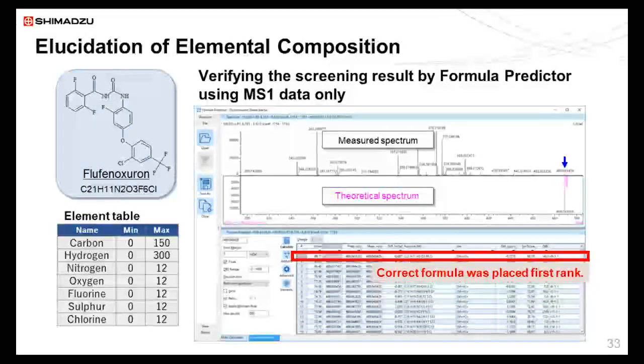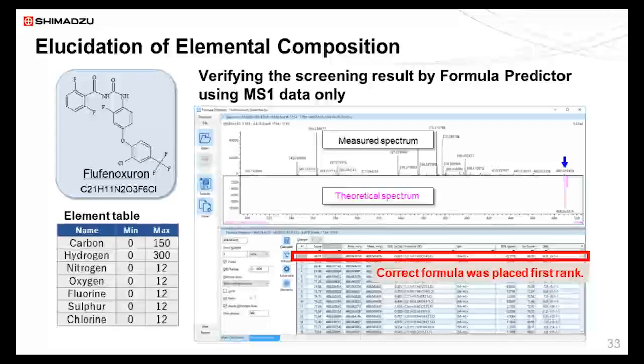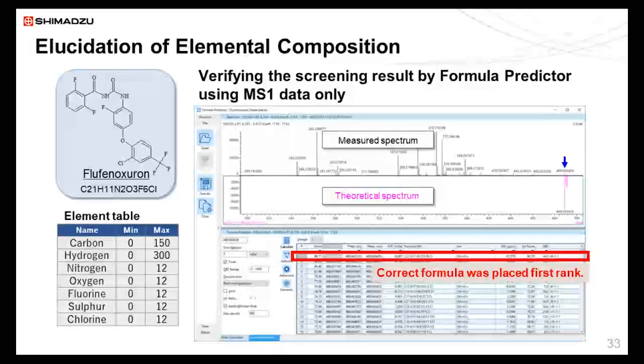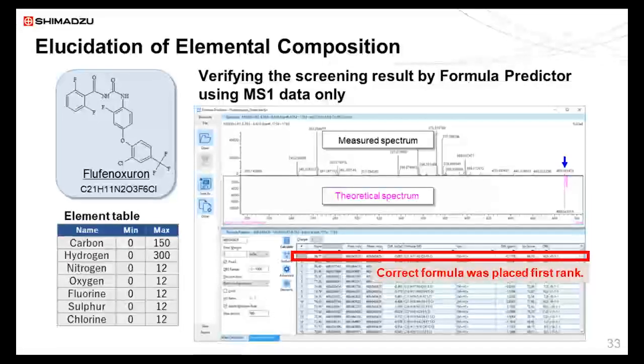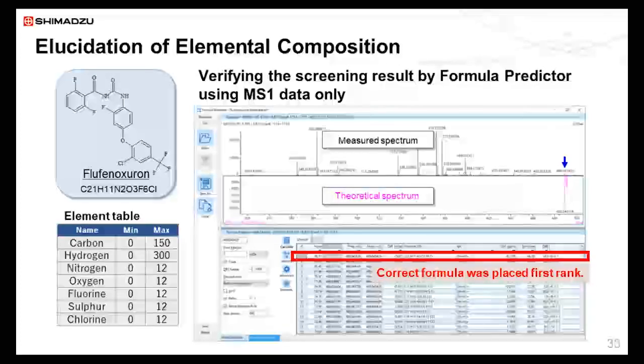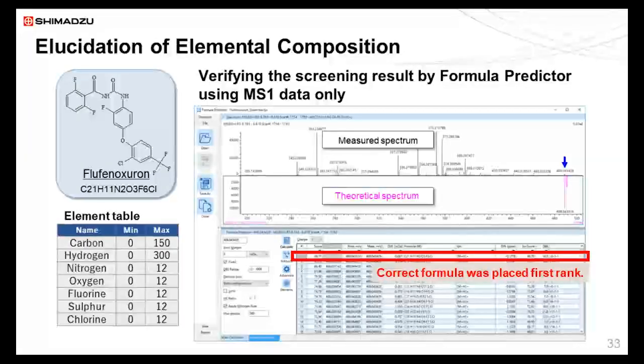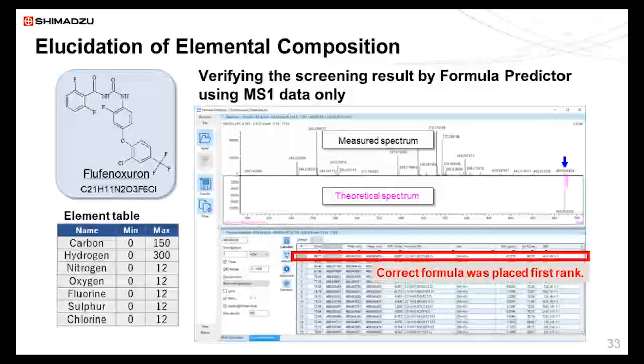But this by itself isn't sufficient for identification. We could further verify this identification by comparing the exact masses and the measured masses, as well as the isotopic abundance ratio. So if we compared the measured spectrum to the theoretical spectrum corresponding to the empirical formula, we could assign correctly that this detected signal was surely of this empirical formula corresponding to Flufenoxuron.